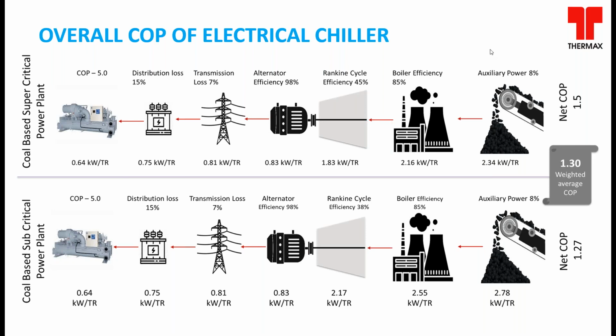So what this means is that even though the electrical chiller is highly efficient, the energy required to drive the electrical chiller is much higher than that is required for an absorption chiller. Generally this point gets missed out, and we just compare the equipment efficiency and we get satisfied at that level.